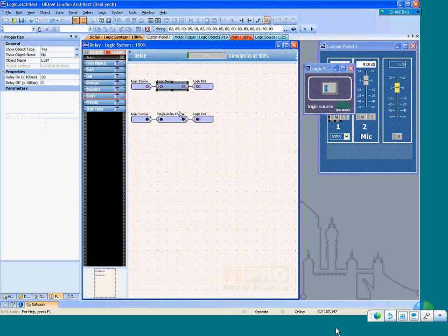What I've done is I go into the logic delay and I set it with a delay on of 3 seconds and a delay off of 0. And I go to the fire marshal and I say, listen, is it okay when the fire panel goes into alarm if the audio system waits 3 seconds before it responds? And I explain to him why. I explain so that when the fire system just reboots itself, we're not getting false triggers. I've never had a fire marshal say no. I've never had anybody say no once I explain the system to it.